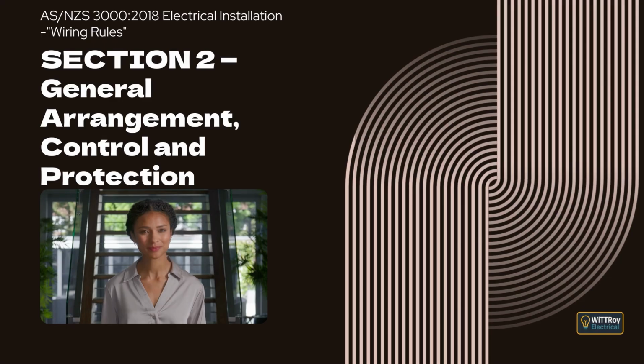Clause 2.6.3.3.3, Home care installations, New Zealand only. Where medical electrical equipment is installed in home care situations, some devices must be protected by a Type I RCD with a maximum rated residual current of 10 mA, and with a faster tripping time. These installations follow the medical standard, AS/NZS 3003.